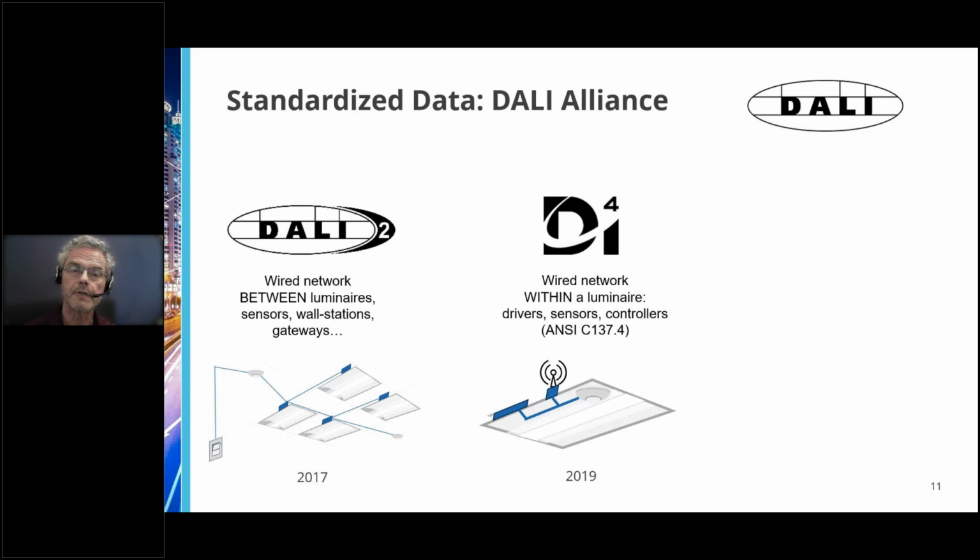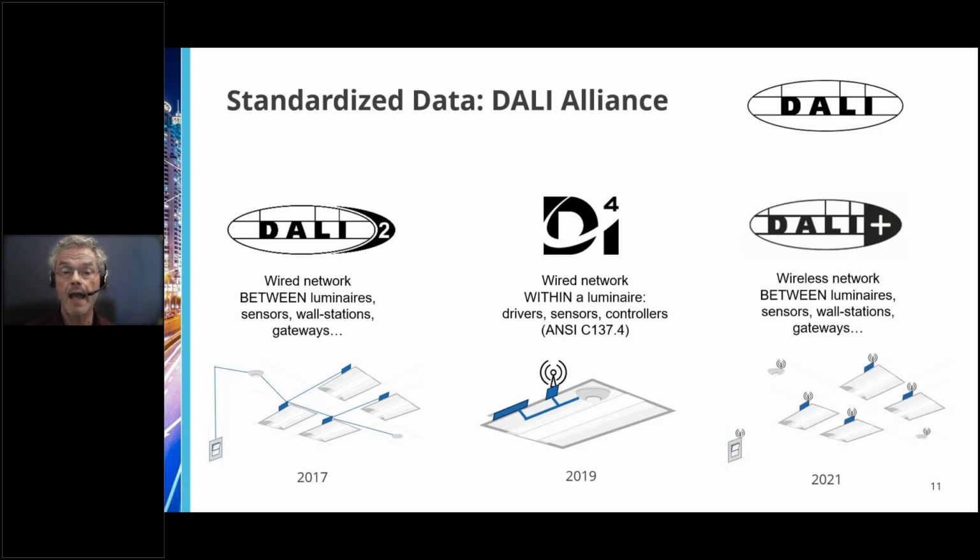LED drivers that support ANSI C137.4 communicate digitally with sensors and controllers and use North American power supplies. This yields standardized digital data that other building systems can interface with. And since 2021, the DALI Plus protocol brings DALI open standardization to wireless networks between luminaires.